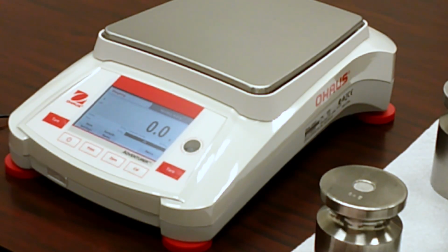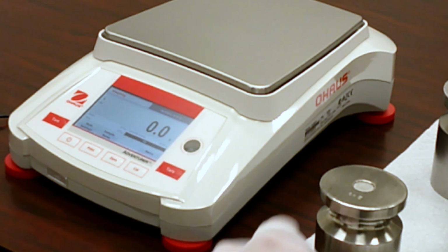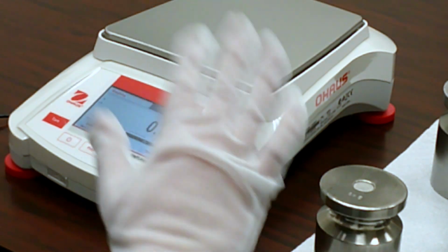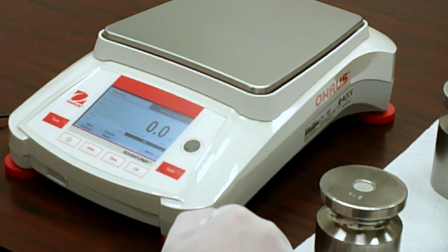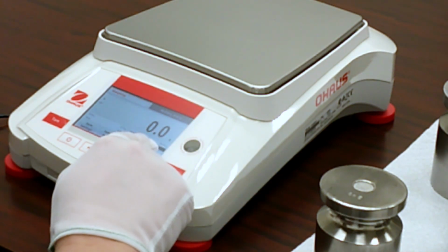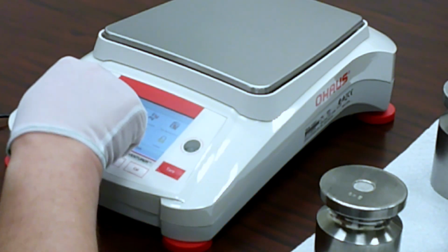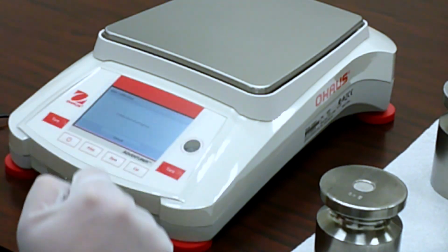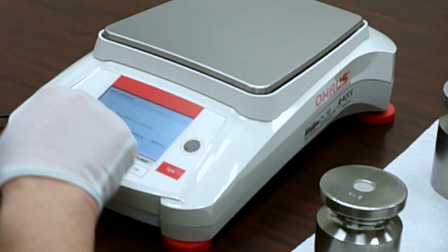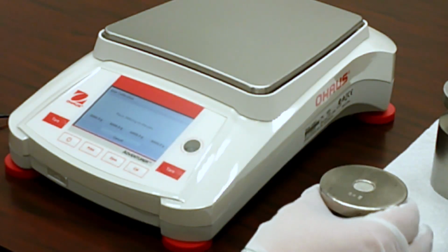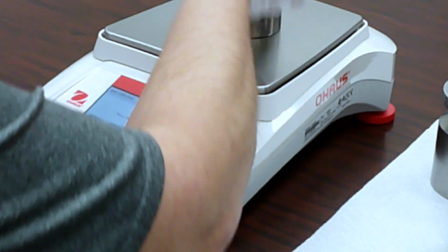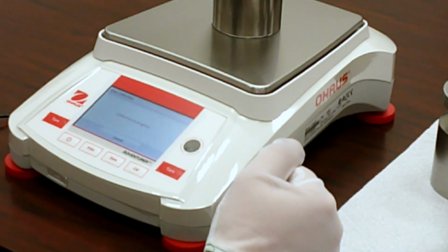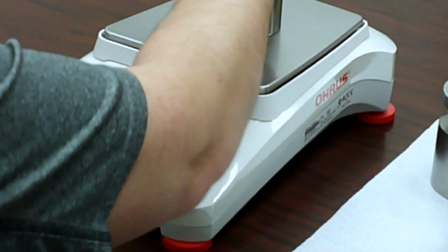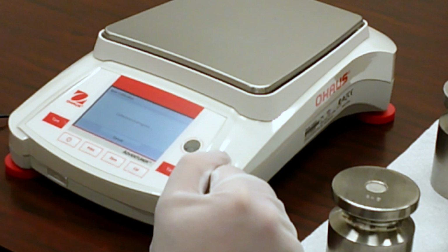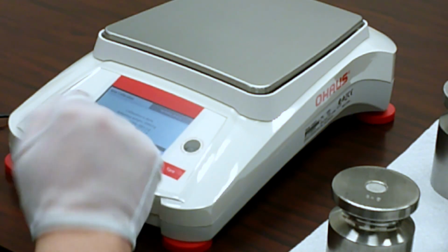Now that we have all of our as-found readings, we can go ahead and make our adjustment. Most balances will use a very simple method, knowing what an empty or zero pan feels like, as well as a known weight value. Most of them will have you go through a menu structure to perform that service, oftentimes called a span calibration. And in this case, we'll be asking to use 2,000 grams for our calibration method. We wait for it to do its thing, we remove it, wait again, and our calibration is complete.